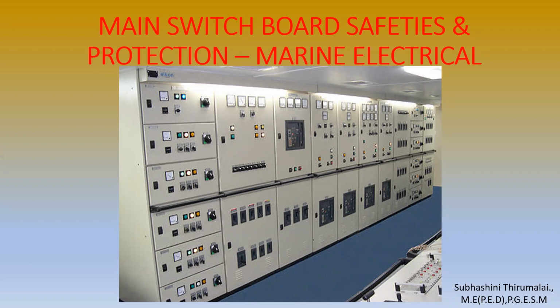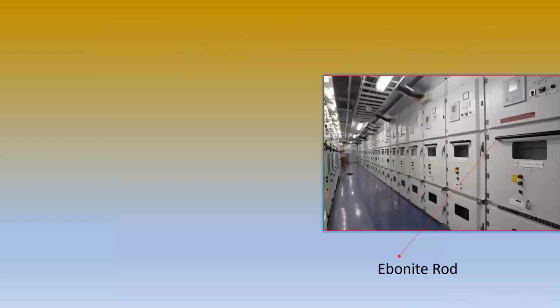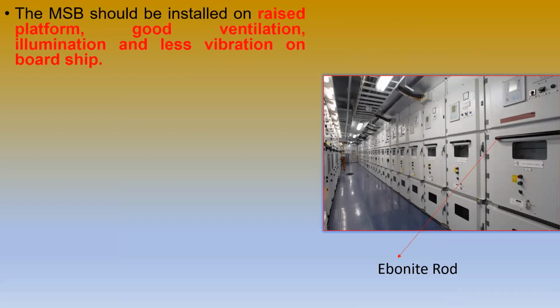So generally, safeties are for human beings as well as for the machineries. So for the lifespan of the machineries, for the lifespan of the main switchboard, and also against shock for the human being. So what are the special safeties? The first point is the MSB should be installed on a raised platform. So to avoid rough sea, rainy season or flood conditions, the water should not enter into the MSB board. So it should be on a raised platform with proper ventilation and lighting system, and less vibration on board ship. The vibration should also be less. So that will be the selected area to install the MSB board. That will be more safe for the main switchboard.